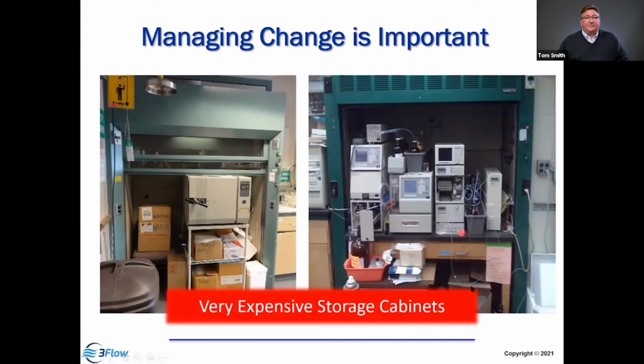This hood right here, because it's 5 feet wide, maybe 6 feet tall, that's 30 square feet. Multiply that by 100 CFM, you've got 3,000 CFM of air. Multiply that by $5 per CFM year, and you're talking a lot of money, 15 grand a year in operational cost for a storage cabinet.